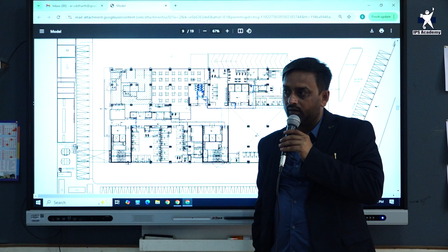Very important. So we got one advantage there, ma'am. At this edge of the building, we were standing with two gen sets. We would have been asked by the government or safety department to take the chimney exhaust to the terrace after 4-5 meters, but we were 20 meters away, so with that we got compliance for stacking at 30 meters of height.